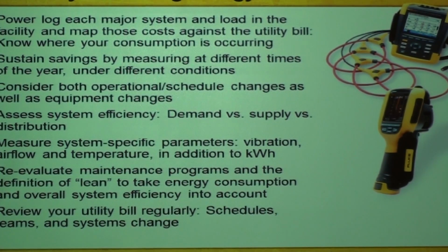It's a repetitive process. Consider operational schedule changes, assess system efficiency in terms of demand versus supply versus distribution, and measure system-specific parameters like vibration, airflow, and temperature, in addition to kilowatt hours. It's not just kilowatt hours for consumption, you want to measure additional things as well.